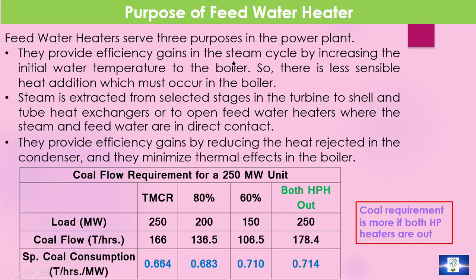Now coming to the purpose of the feed water heaters, meaning why feed water heaters are required in a thermal power plant. It is required because feed water heaters allow the feed water to be brought up to the saturation temperature very gradually. So they provide efficiency gains in the steam cycle by increasing the initial water temperature to the boiler. So there is less sensible heat addition required which must occur in the boiler.